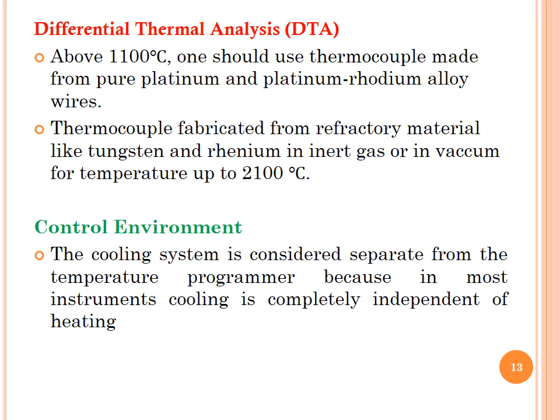Control environment. The cooling system is considered separate from the temperature program because in most instruments cooling is completely independent of heating.